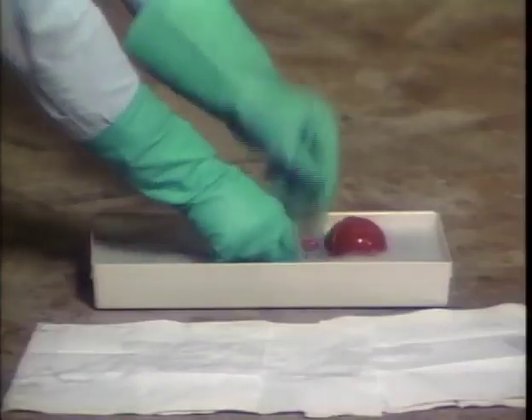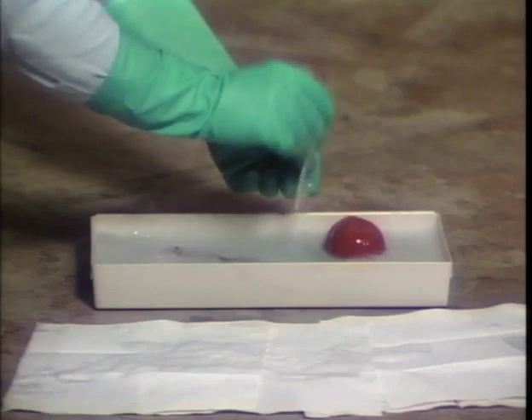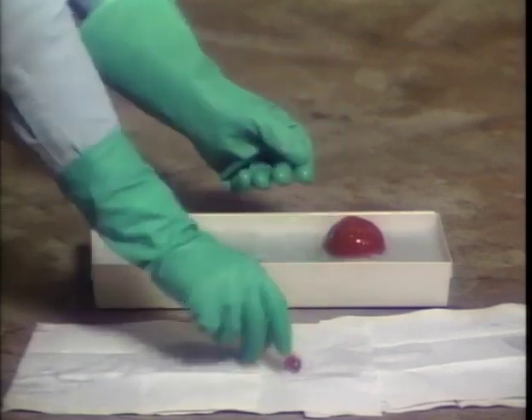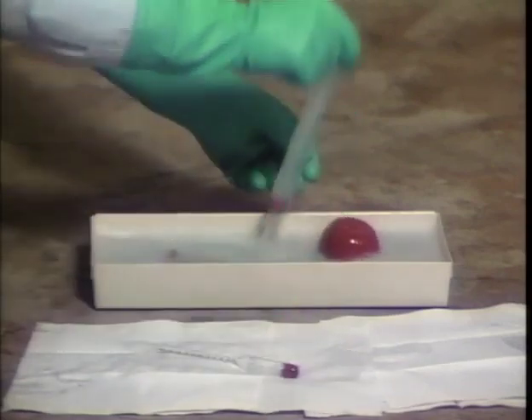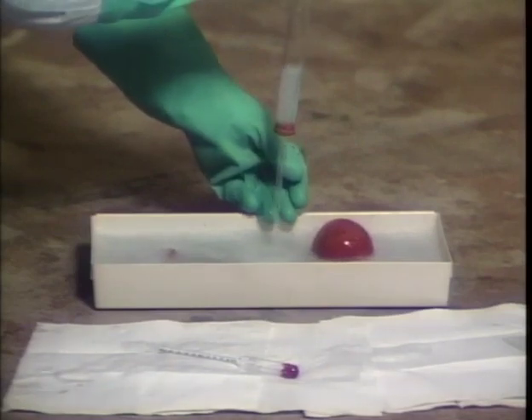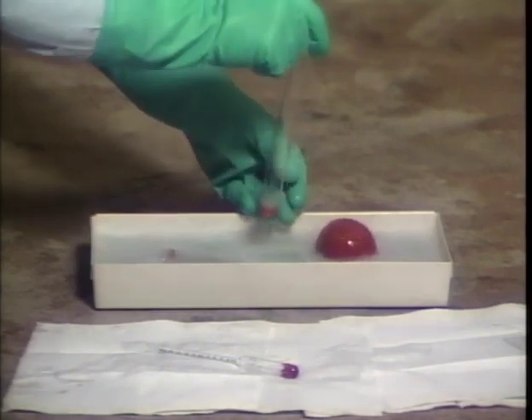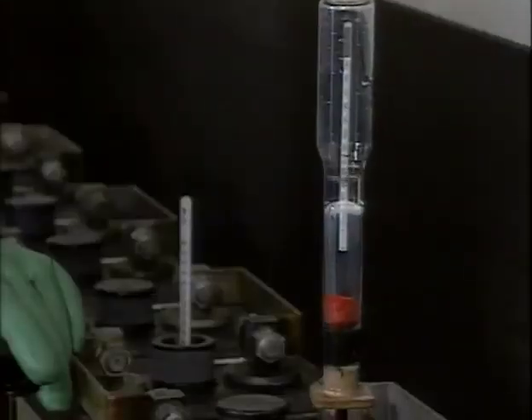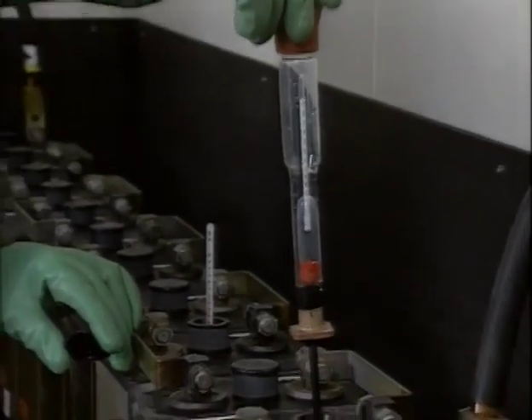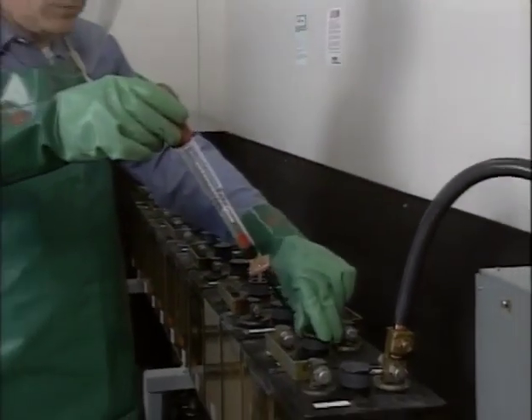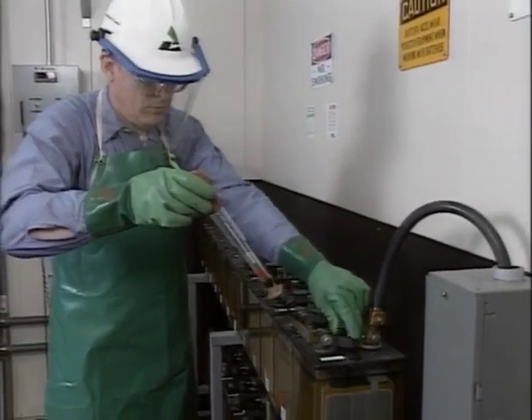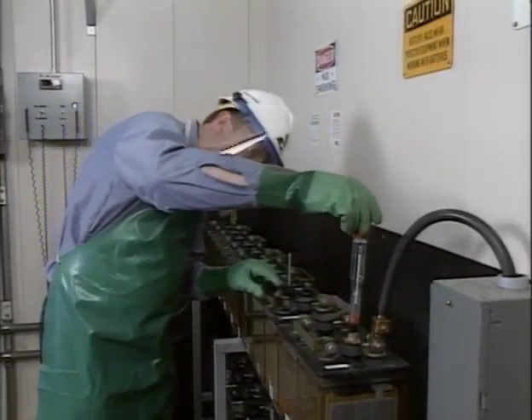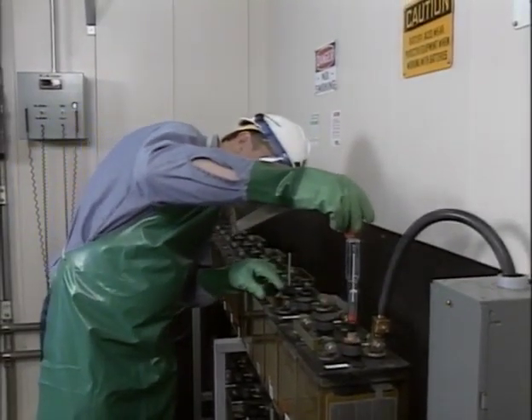Finally, it's a good practice to regularly disassemble and wash the hydrometer syringe with soap and water. This helps prevent a buildup of sulfuric acid that can cause small errors in specific gravity readings. Specific gravity tests, if done at the right time and when properly corrected for temperature, give a good indication of the state of charge of the cells in a battery.